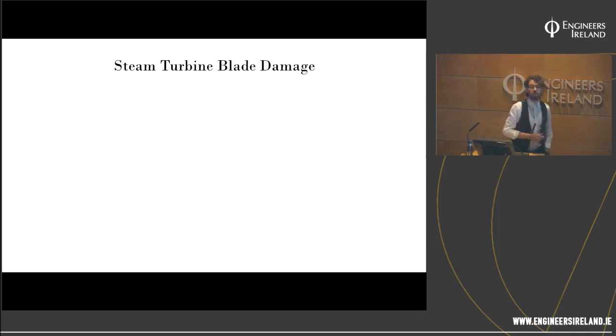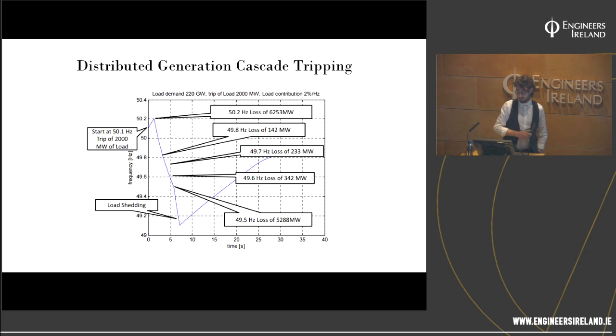How does the frequency go back up if there's no generators on air? Sorry? How does the frequency go back up? So right at the end, there's load shedding. So there's involuntary customers shed at that point to make the balance back up. So you presume people are being signaled to switch off certain loads? No, you're shut. Unless you're a hospital, you're coming off. There'll be a blackout. So every power system in the world will have load shedding, and it's kind of the goal of the TSO to make sure that doesn't happen, in an economic fashion.